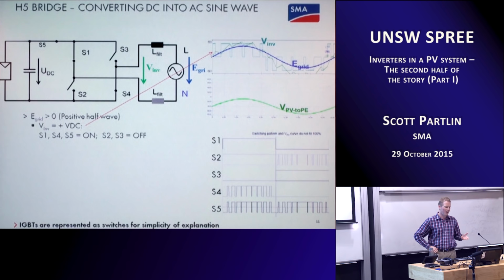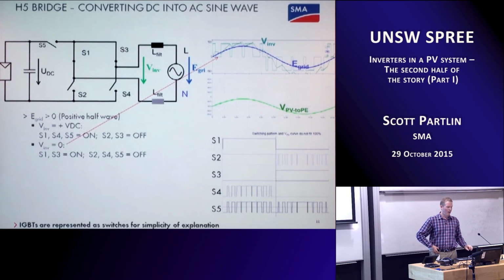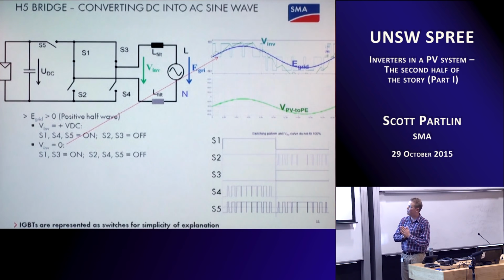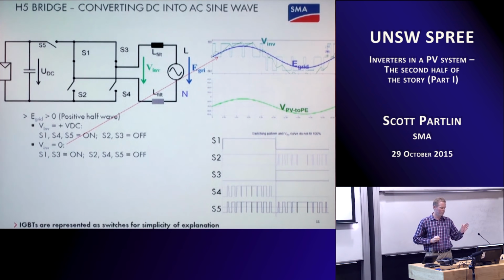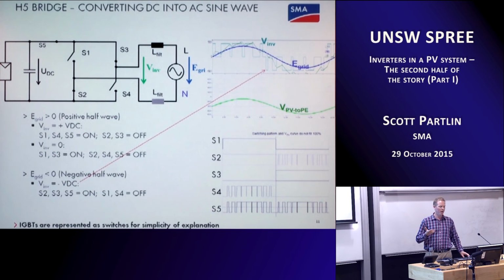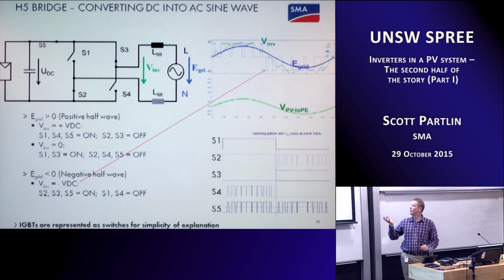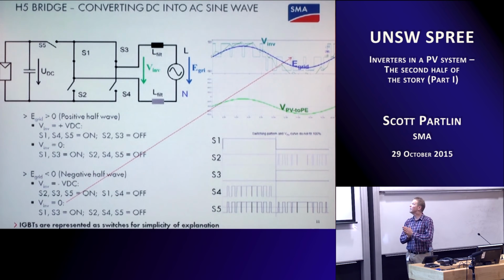So in the first step we've got positive DC voltage. In the next step we start making our zero point, so zero DC voltage: switch 5 opens, switch 1 remains closed, switch 3 closes, and we start generating a very ugly, stepped sine wave. Then in a third step we generate the negative part of our AC sine wave and complete it down to a minimum.